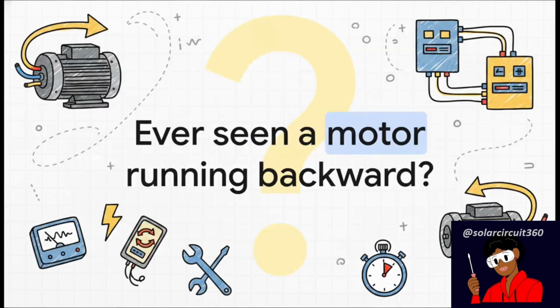That's it. Once you re-energize, the rotating magnetic field will completely flip and your motor will run perfectly in the correct direction. It really is such a fascinating intersection of invisible electrical theory and highly visible mechanical reality, isn't it? So I've got to ask, have you ever encountered a motor running backward out in the field after an inverter installation, a generator hookup, or maybe just a routine maintenance visit? How long did it take for you to realize that your trusty meters were lying to you and the phase sequence was the real culprit? Let that sink in next time you're staring down a perfectly balanced, completely non-functional system.